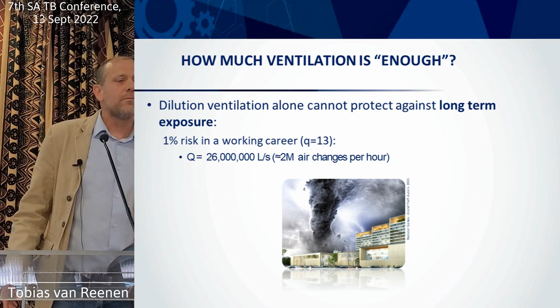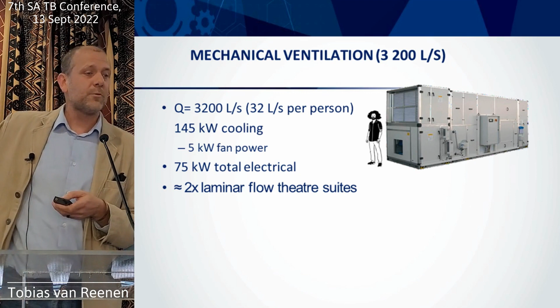That's what the air handling unit looks like to give us that much air. It's a big boy, the kind you'd typically use in laminar flow theatre suites. It requires 145 kilowatts of cooling, about 5 kilowatts for fan power, giving about 75 kilowatts total electrical. For those that work in horsepower, that's what 100 horses looks like. It's a massive amount of power, a lot of energy, big capital cost to ventilate these waiting rooms using mechanical ventilation. It's about the airflow we use for two laminar flow theatre suites, complete suites.